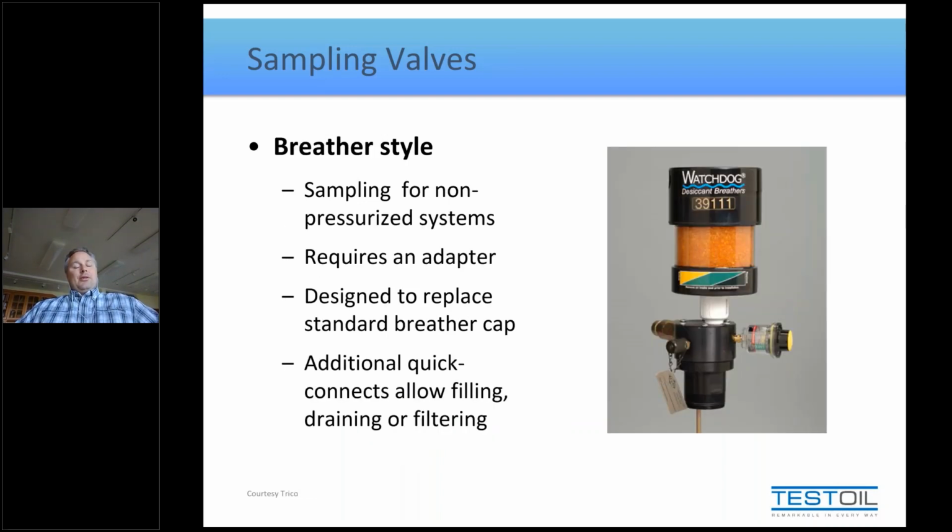But this one here, this is the third most common one that I recommend. I like to recommend the pitot tubes. I like to recommend the bullseye sight glass ones. And I also, for some of the reservoirs, particularly on hydraulic systems, like to recommend this one. If you're familiar with the quarter-turn breathers, the little gaskets they have underneath them, this basically, you remove the collar that holds that basket, and this manifold threads into the same 3 or 6 hole bolt pattern.